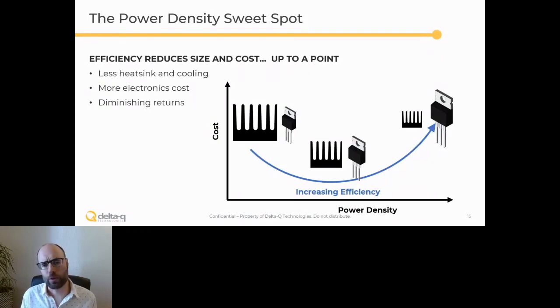With a sealed charger, things are very different from unsealed off-board power electronics, like a rack-mount power supply for telecom or UPS backup power, where you can blow a fan through an open frame box. With a sealed box, all the loss you generate, all the heat, has to come out by conduction. Whether you have liquid cooling, fan cooling, or passive cooling, you have to conduct that heat to the outside of the box. So the size of the box and the heat sink, particularly when passively cooled, is driven in large part by efficiency.